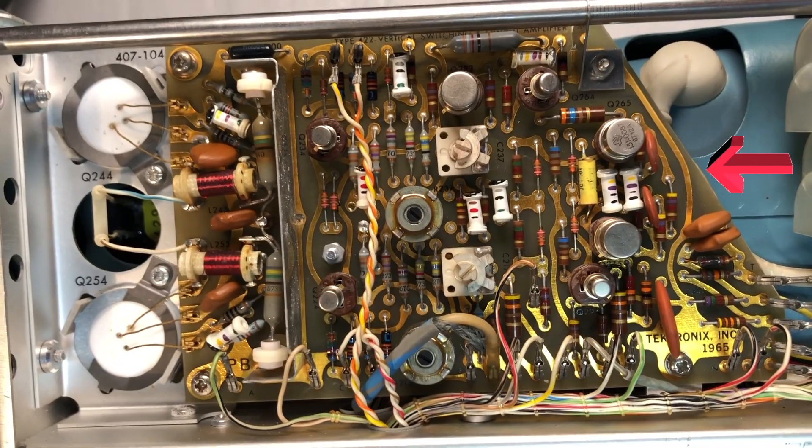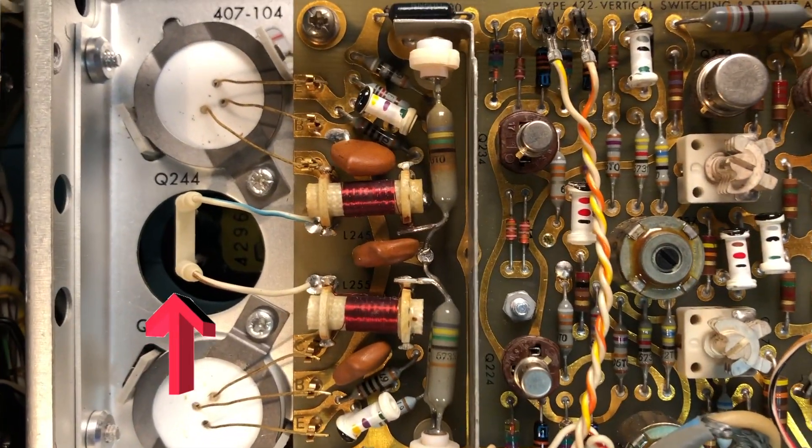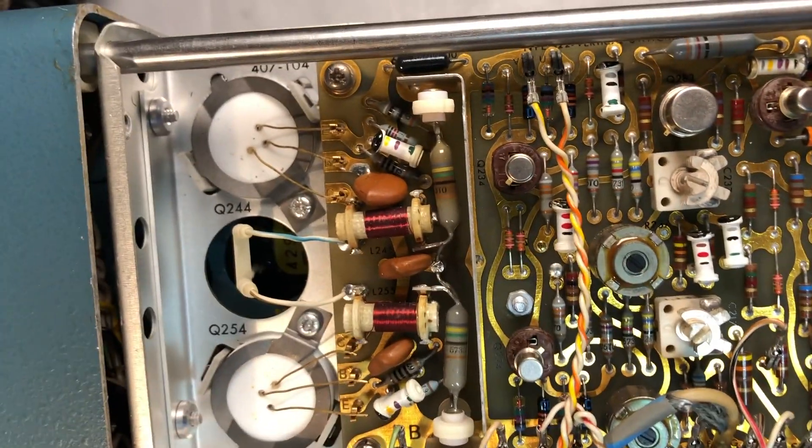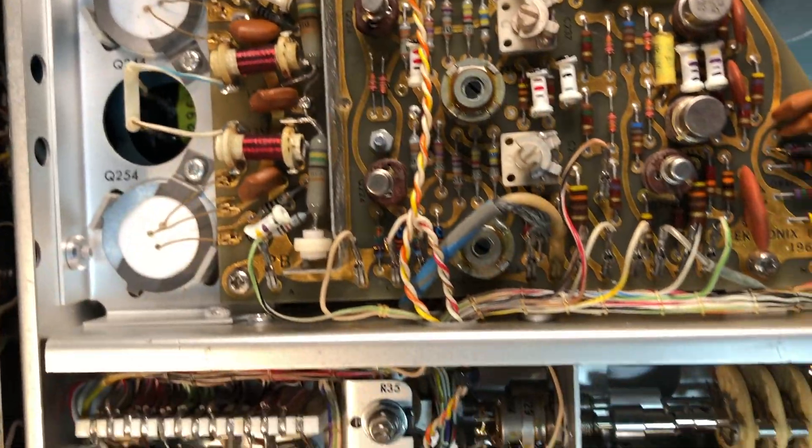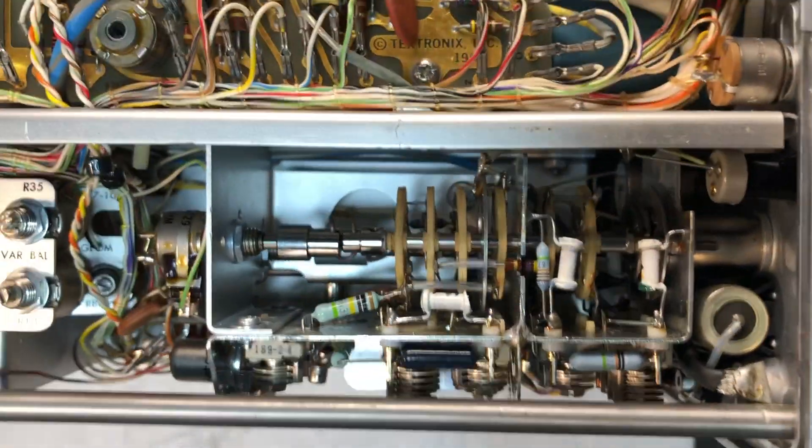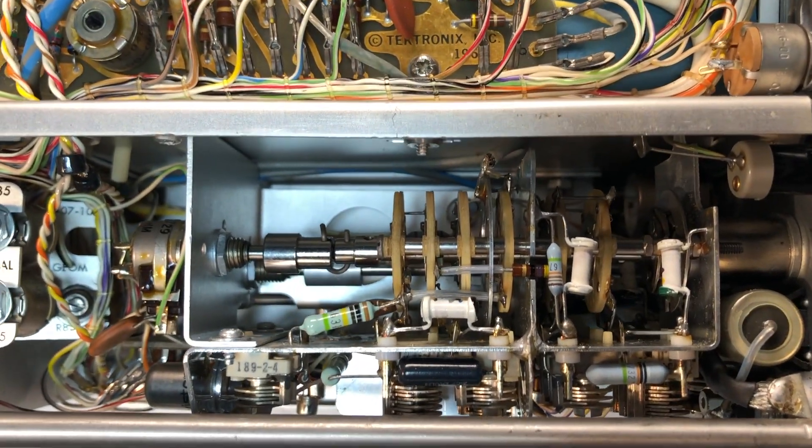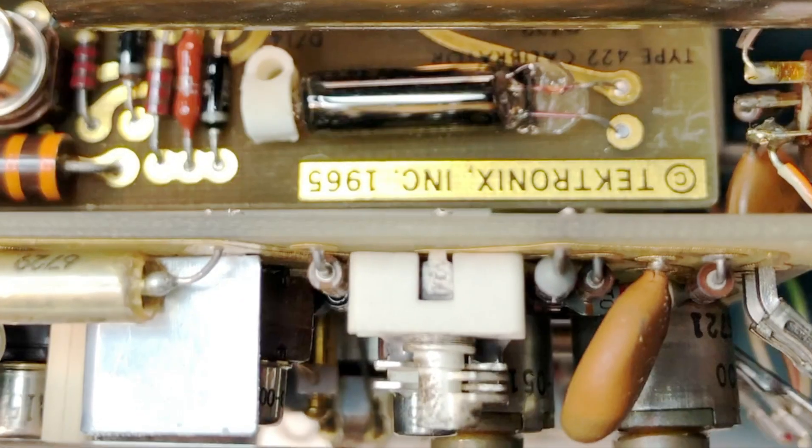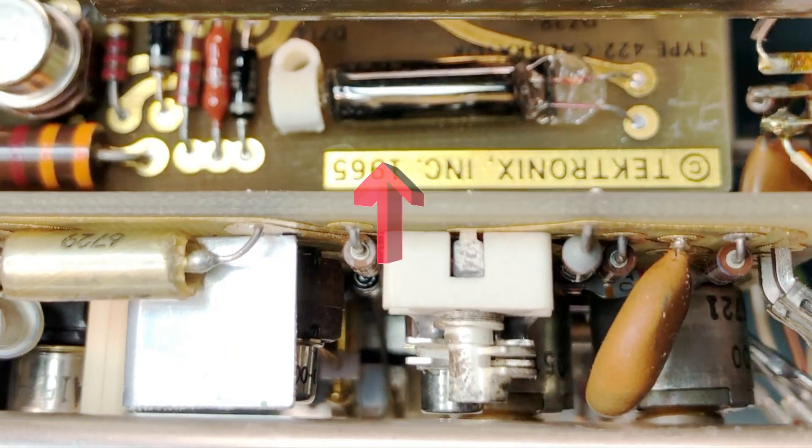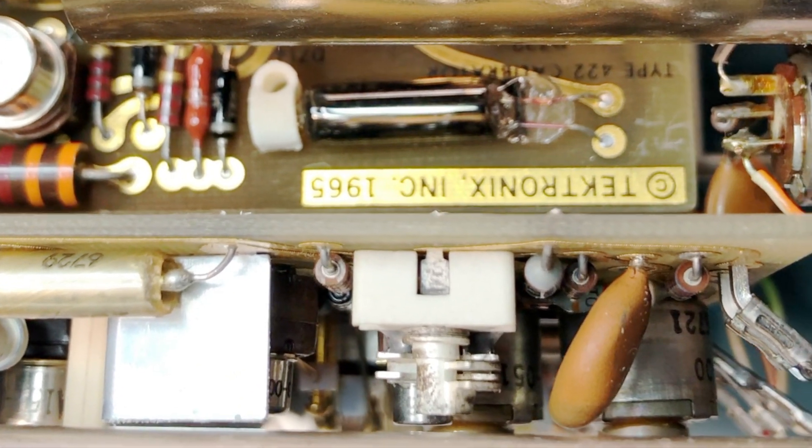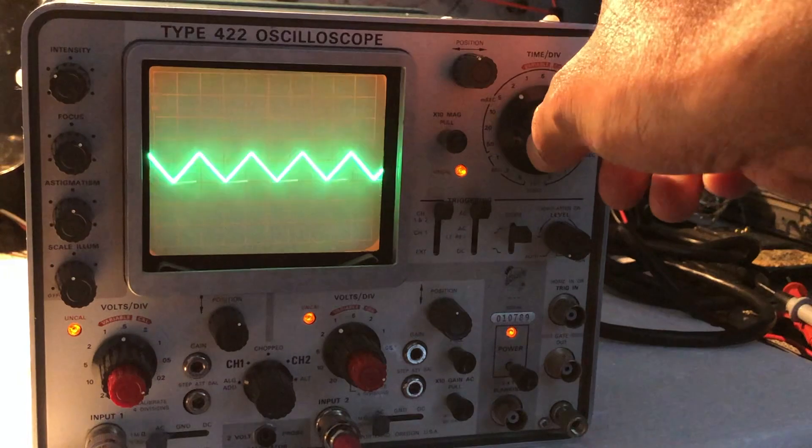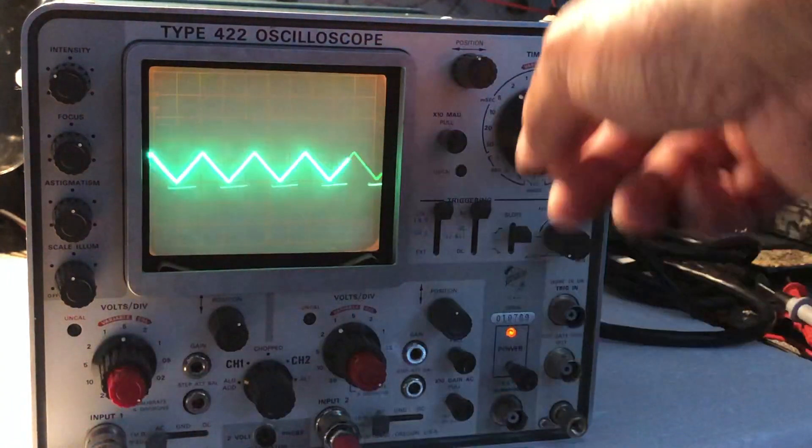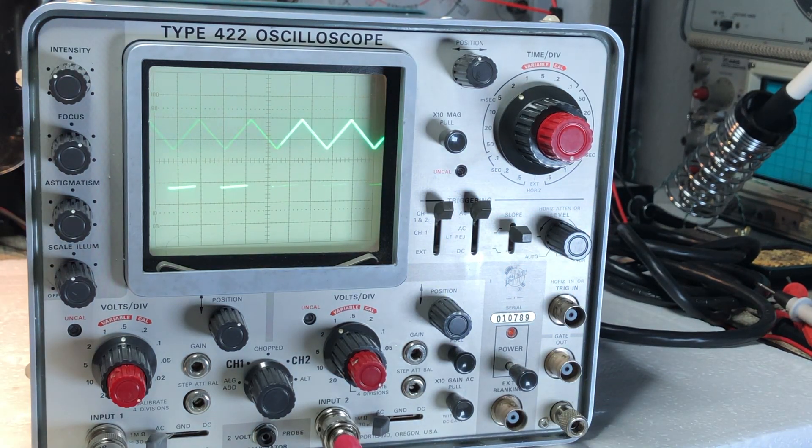Finally, this is the left side of the instrument, which is mainly the vertical amplifier board or the final vertical amplifier in connection to the CRT plate. Q254 and Q244 are the vertical output transistors. Test point and some part of the attenuator for channel one. Nuvistors here in the trigger board as well. On the regulator board there's one more VR tube. It's kind of interesting that they used a mix of zener diodes and voltage regulator tubes. That's one happy looking scope there. Let me move all the controls to calibrated position. That's it. Thank you so much for watching and take care.